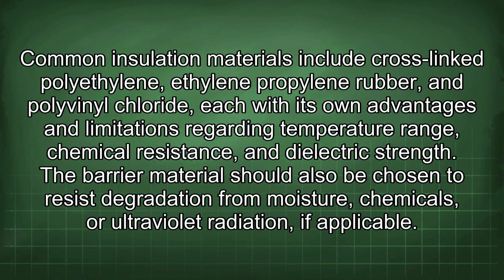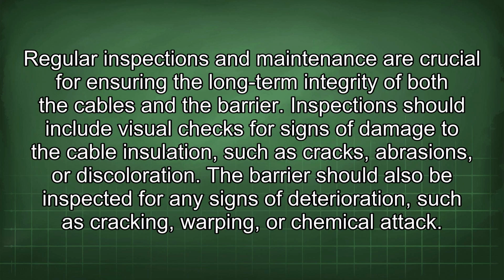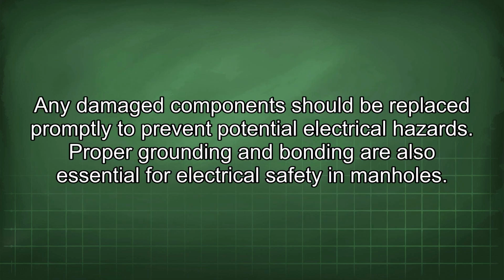The barrier material should also be chosen to resist degradation from moisture, chemicals, or ultraviolet radiation, if applicable. Regular inspections and maintenance are crucial for ensuring the long-term integrity of both the cables and the barrier. Inspections should include visual checks for signs of damage to the cable insulation, such as cracks, abrasions, or discoloration. The barrier should also be inspected for any signs of deterioration, such as cracking, warping, or chemical attack. Any damaged components should be replaced promptly to prevent potential electrical hazards.